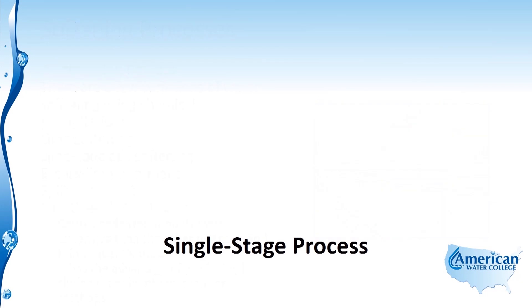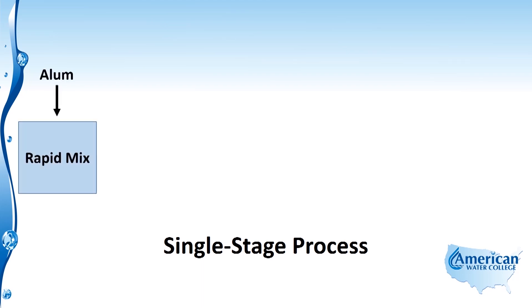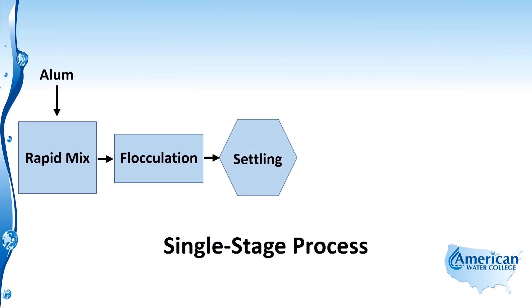The most common method is the single stage process, which is very similar to a conventional treatment plant. It starts with a coagulant — in this case alum — added to the rapid mix tank. The water then moves on to the flocculation chamber, and from there into the settling basin.